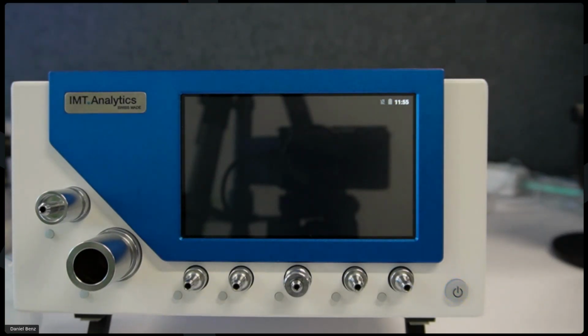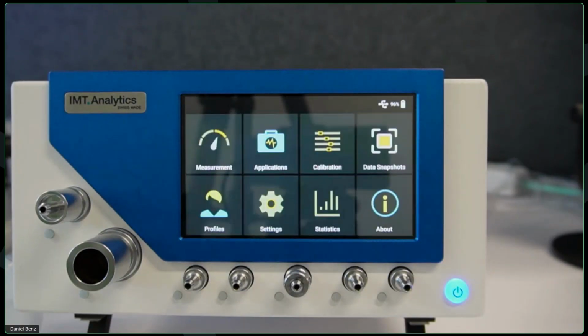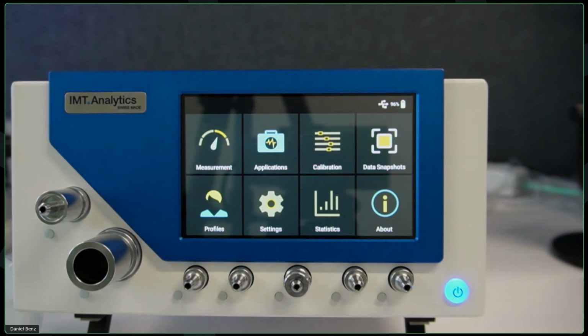We call all our devices all-in-one devices, so that's actually our concept. The reason is that everything else you typically need to measure in ventilation applications is also being measured right inside this main flow channel. So we are not only measuring flow here, but also the gas pressure, temperature, humidity, and oxygen of the gas mix. It's all measured inside this channel. So all the compensations for the flow and volume calculations are then made automatically, and there is no need to tee in any sensor or pressure lines here. We will see that later when we set up the ventilator.